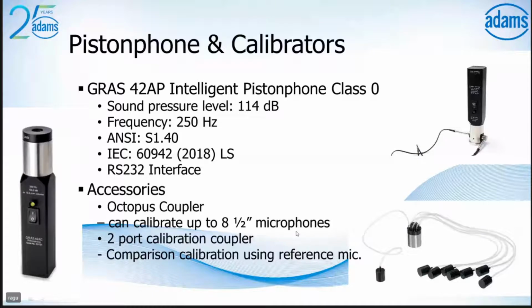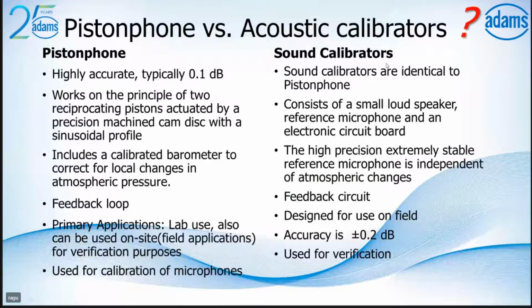So piston phone and calibrators. What is basically the difference between the two? Almost both of them are similar, but the piston phone is highly accurate and more precise compared to the sound calibrator. It includes a calibrated barometer for correction for local changes in atmospheric pressure. So laboratories should consider going for a piston phone and use it for calibration.